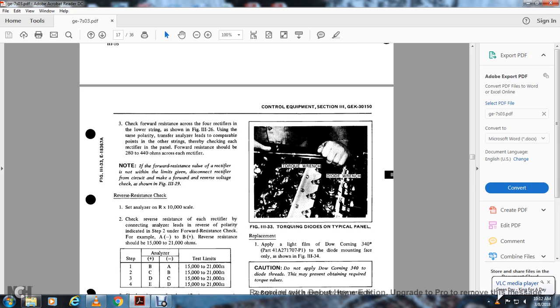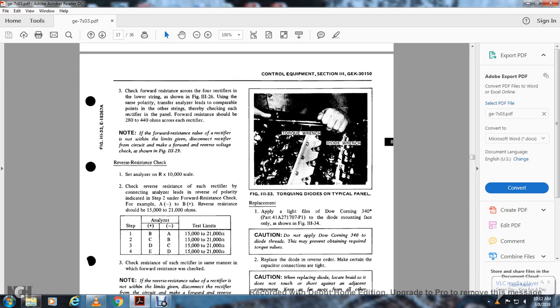Note that if the forward resistance value of a rectifier is not within the limits given, disconnect the rectifier to make the forward and reverse voltage check shown in figure 329. Reverse resistance check: set the analyzer R to the 10,000 scale. Check the reverse resistance of each rectifier by connecting the analyzer leads with reversed polarity from the forward resistance check. For example, A negative, B positive. The reverse resistance should be 15,000 to 21,000 ohms. All test limits are 15,000 to 21,000 ohms.